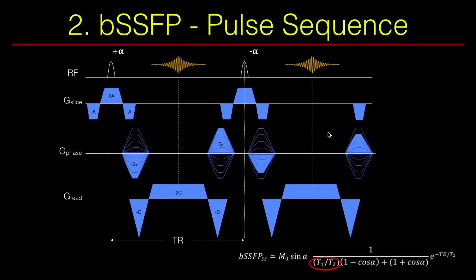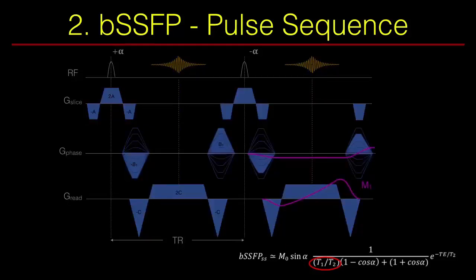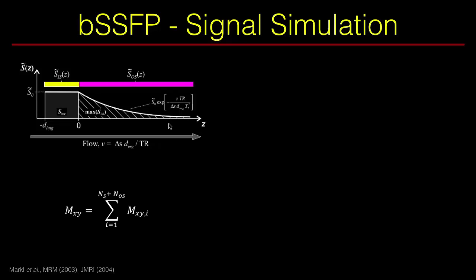The second sequence is balanced SSFP. All gradients on all axes are completely compensated — the zeroth-order gradient moment is zero in all three axes, making it very well flow-compensated. The M1 moments are also very close to zero at echo time. The steady-state signal of balanced SSFP is T2/T1 weighted. Signal computation in balanced SSFP in the presence of flow is more involved because of complete refocusing gradients: even after spins exit the imaging slice, they still contribute to the signal. The total signal is the summation of contributions from both the excited slice and out-of-slice spins.